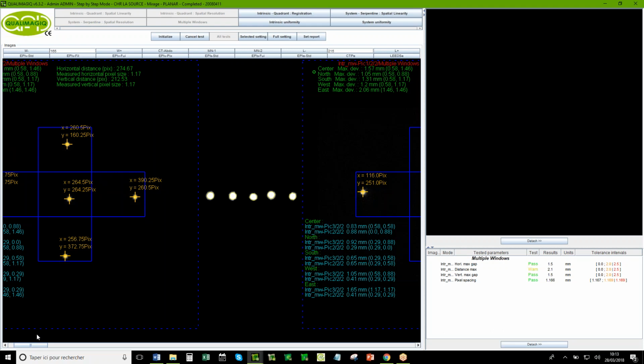Of course, it's impossible to imagine you do a first acquisition with 1 radioactive source, you remove the plate, you install a second one. No, it's not like that. You need a radioactive source with 2 energy peaks. So minimum, I think you need to use an indium source, and you have the 2 energies with an indium source. Do you use indium in your department?